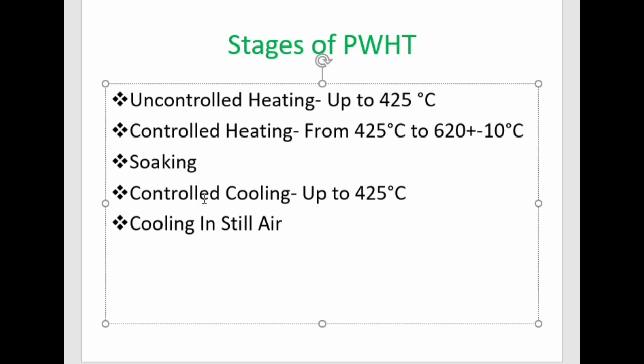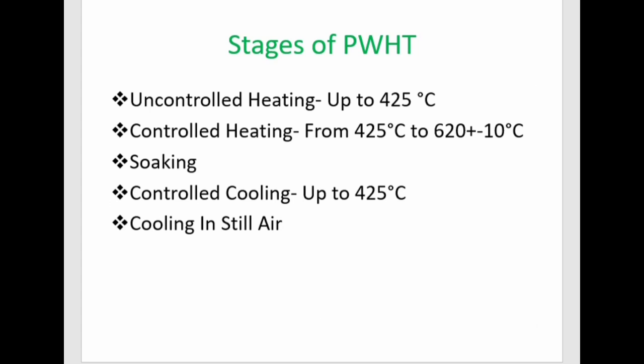The third stage is soaking — the process of keeping the pressure vessel at a particular temperature for a particular time period in order to relieve stresses. The fourth stage is controlled cooling from the soaking temperature of 620°C down to 425°C. The fifth stage: below 425°C, the vessel may be cooled in still air.